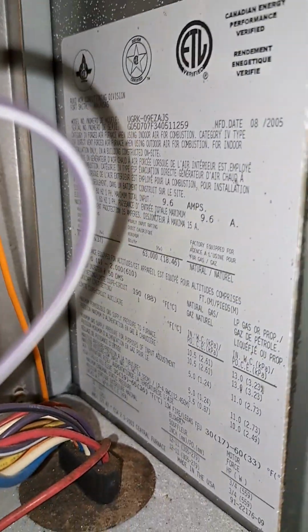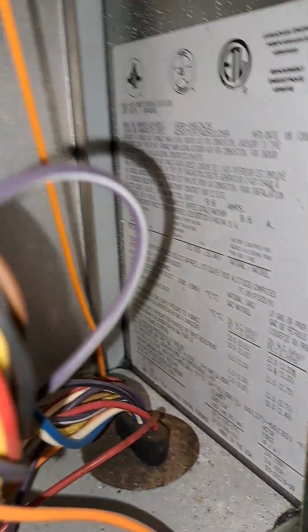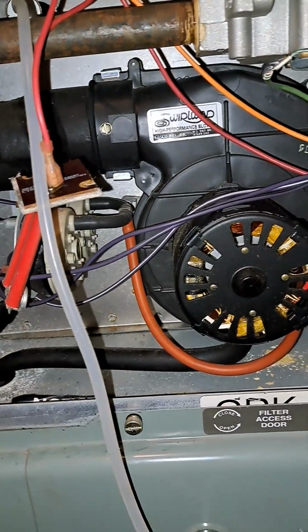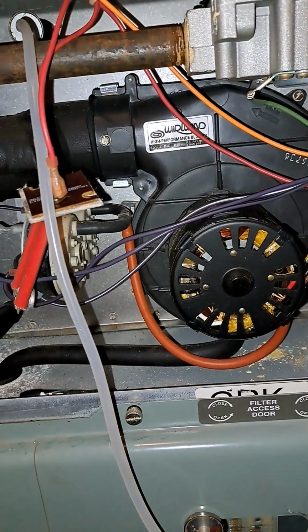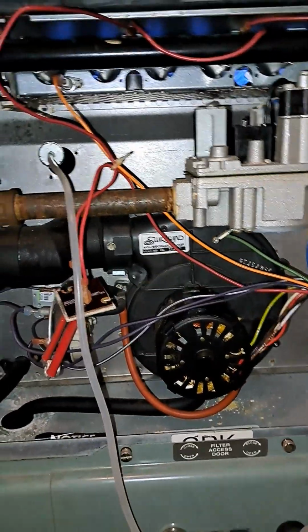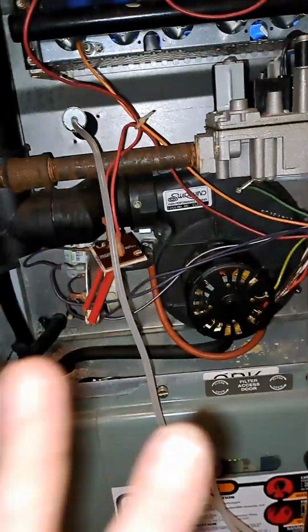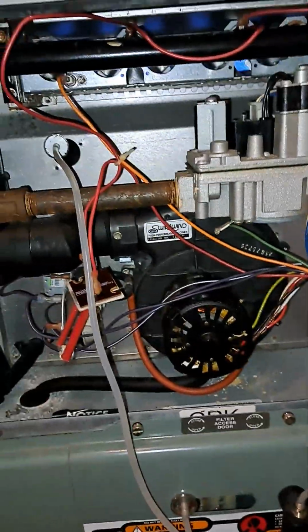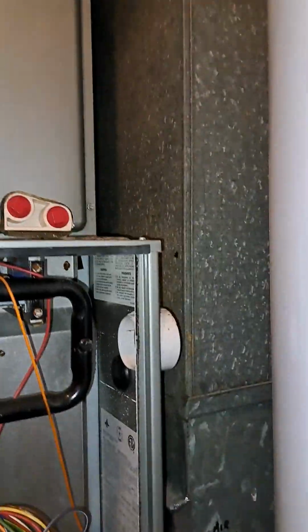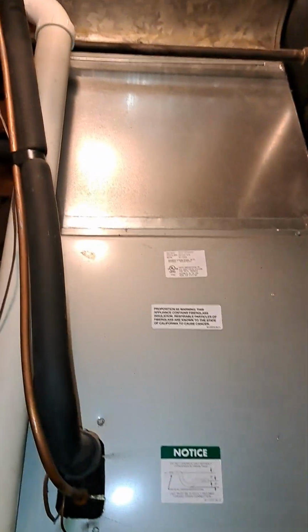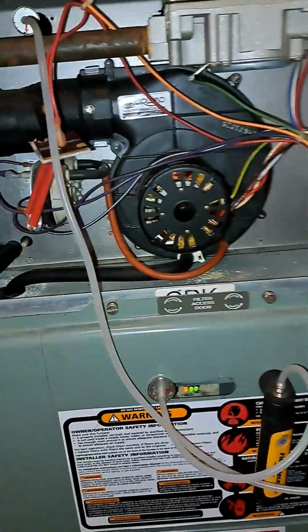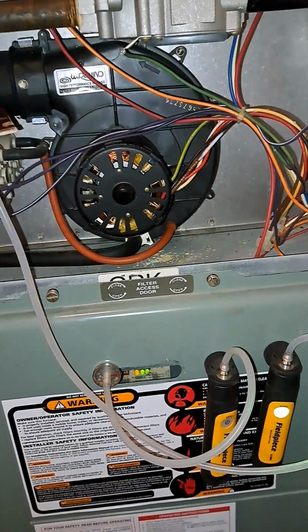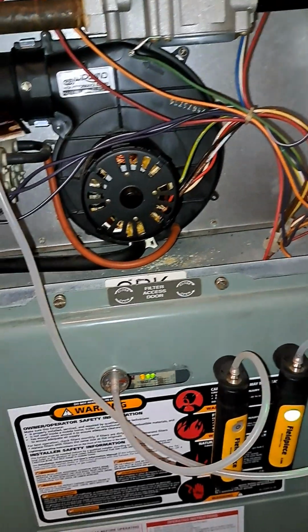Usually there's a rating of total static pressure on the data tag. I find that 0.5 is ideal. You typically don't want to go over 0.7 if you can, so 0.2 to 0.7 would be an allowable range. Anything over that, I would start looking at your ductwork and airflow restrictions. Things of this nature are going to increase that.